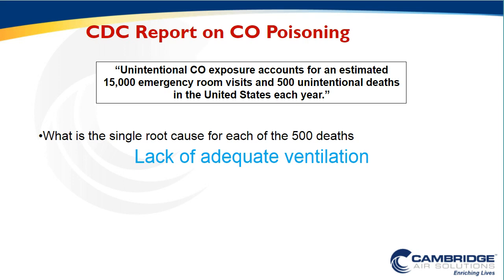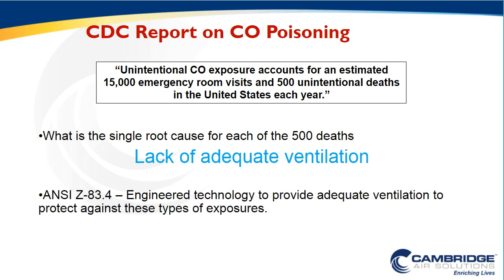And in most cases where we do have CO detection systems, maybe parking garages, when we see those CO levels reach an unsafe level and we have those sophisticated controls, the immediate next step is to increase our ventilation, to turn on our ventilation systems, to reduce those CO levels. And if we think back to the core performance of the technology we're talking about today, these systems are 100% outside air and they are designed to provide ventilation. There is no way that you can separate the ventilation component from the combustion component of these technologies, such that you will always be ventilating whenever you're combusting. You will always be bringing in fresh air whenever you are heating.